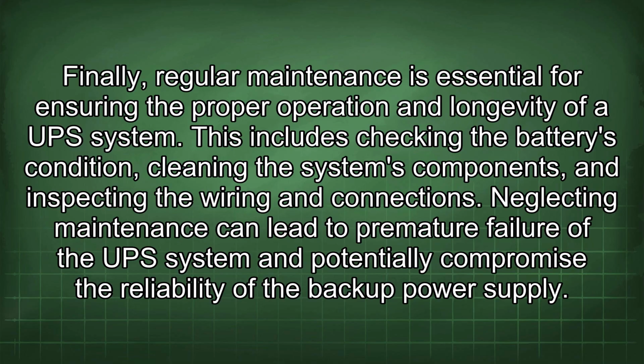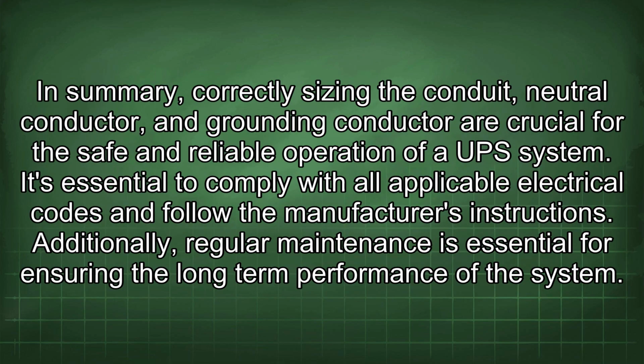Finally, regular maintenance is essential for ensuring the proper operation and longevity of a UPS system. This includes checking the battery's condition, cleaning the system's components, and inspecting the wiring and connections. Neglecting maintenance can lead to premature failure of the UPS system and potentially compromise the reliability of the backup power supply. In summary, correctly sizing the conduit, neutral conductor, and grounding conductor are crucial for the safe and reliable operation of a UPS system. It's essential to comply with all applicable electrical codes and follow the manufacturer's instructions. Additionally, regular maintenance is essential for ensuring the long-term performance of the system.